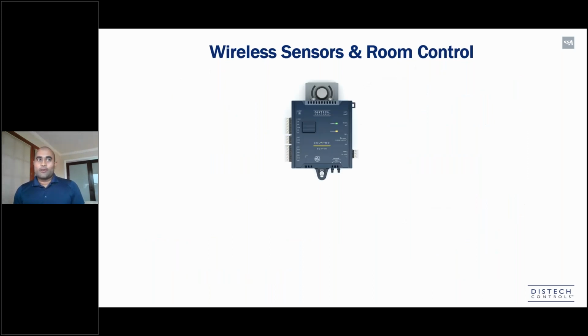We've all seen some level of VAV boxes. They're usually pretty standard, straightforward equipment with a sensor input and a built-in actuator that turns the damper open or closed depending on how much air, heat, or coolness you need. Those days are gone though. This is not your usual VAV box anymore. What's happening now is they are taking on multiple capabilities.